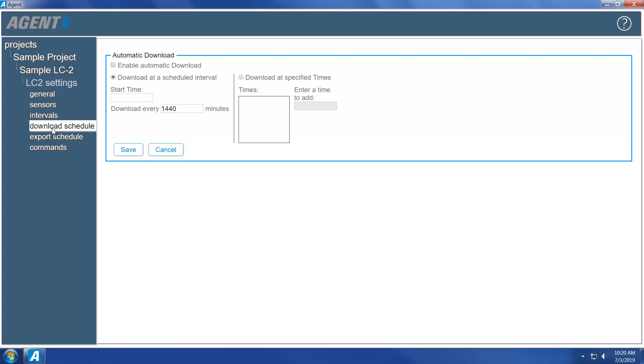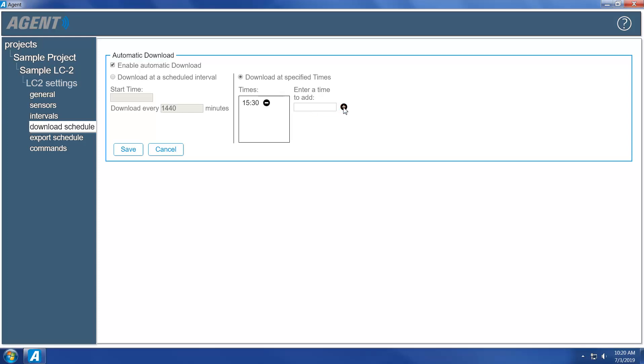Check the box next to Enable Automatic Download. To set Automatic Download to occur at specific times, click the Download at specified times button. These times must be entered in 24-hour format — for example, 3:30 PM would be entered as 15:30. Click the plus sign to add the time to the list of download times. To remove a time from the list, click the minus sign. To set Automatic Download to occur at scheduled intervals, click the Download at a scheduled interval button. Enter a start time in 24-hour format and an interval in minutes. The interval is required; the start time is optional. When finished editing the Automatic Download settings, click Save.